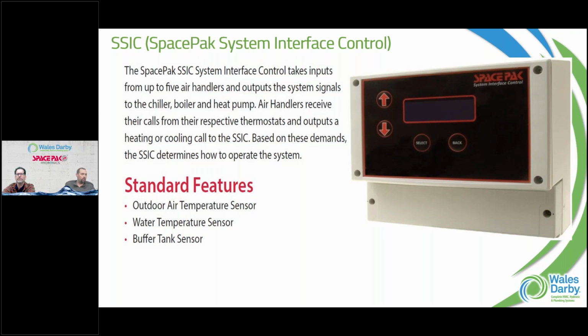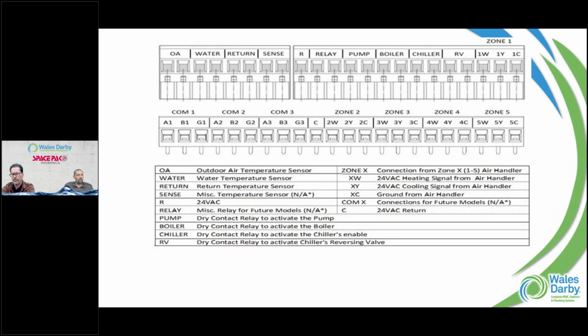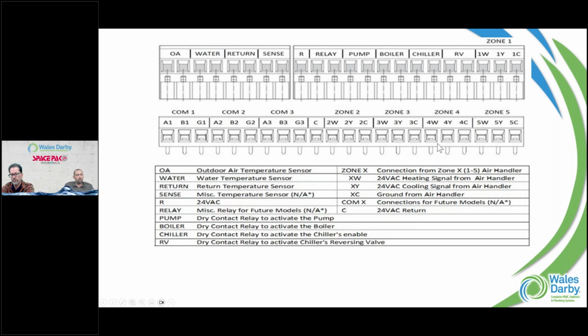This is going to take information like, if you look at the diagram, we have landing spots here for our heating and cooling coming back from whatever zones are hooked up to the system. Depending on which one of these gets energized first, that's going to tell the outdoor unit whether it needs to be heating or cooling.